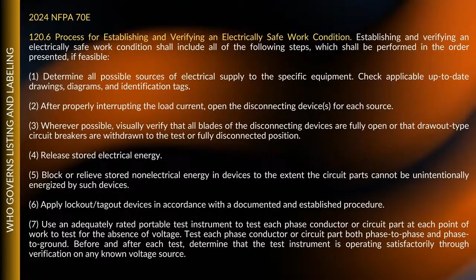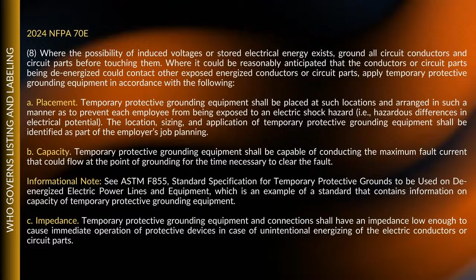100%. Now, number 8 talks about where the possibility of induced voltage or stored electrical energy exists: ground all circuit conductors and circuit parts before touching them, where it could be reasonably anticipated that the conductors or circuit parts being de-energized could contact other exposed energized conductors or circuit parts. Now listen to this. Apply temporary protective grounding equipment in accordance with the following, and it talks about the placement, capacity, and impedance of it. That just goes back to doing your grounding on the system, where you're trying to release some stored energies.